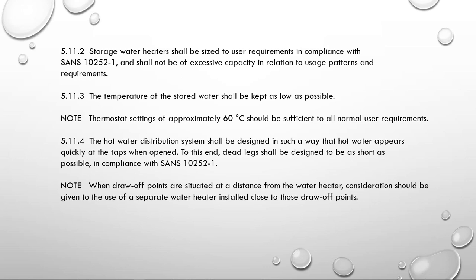We also have to limit the size of our dead legs. Clause 5.11.4 says the hot water distribution shall be designed so that hot water appears quickly at the taps when opened, and dead legs shall be designed to be as short as possible in compliance with SANS. Instead of having one geyser supplying two or three areas, it may be better to resize and put a smaller geyser at each area of the installation to keep dead legs as short as possible.